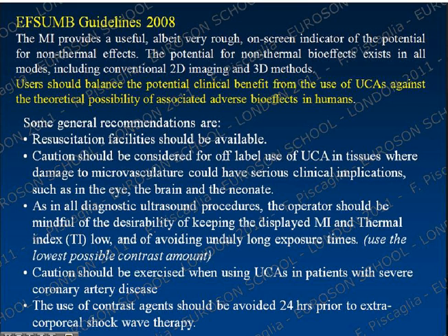As in all diagnostic ultrasound procedures, the operator should be mindful of the desirability of keeping the displayed mechanical index and thermal index low and of avoiding unduly long exposure times. And caution should be exercised when using ultrasound contrast agents in patients with severe coronary artery disease. This is clearly expressed. It is only a caution. It is not a complete contraindication.